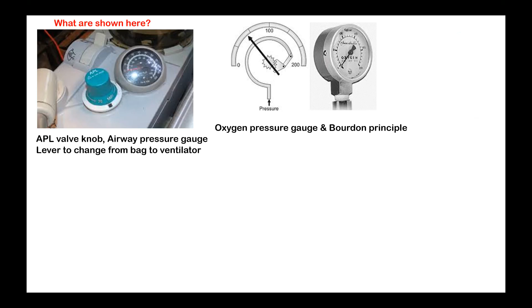And the unit of the anesthesia machine consisting of a gas outlet, pressure gauge, pressure regulator. This portion is the pressure regulator, and this is the downstream pressure outlet. From here only it goes to the flow meter. So this is the entry point for gases from the cylinder or pipeline. Then immediately the pressure will be reflected. That pressure is reduced by this pressure reducing valve, and then further downstream it goes to the flow meter. So this is the assembly you will see in the older machines, and which will be hidden in the newer machines.